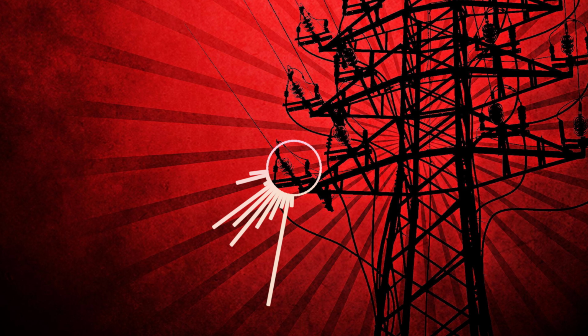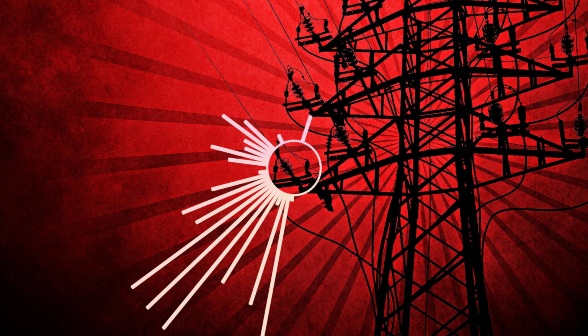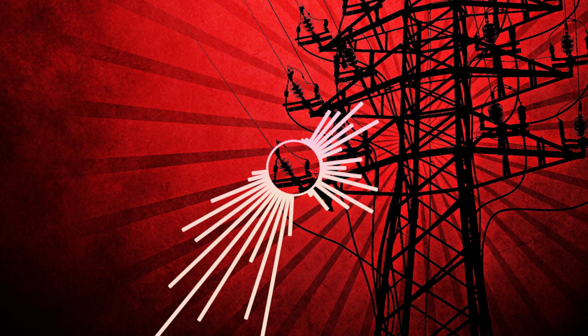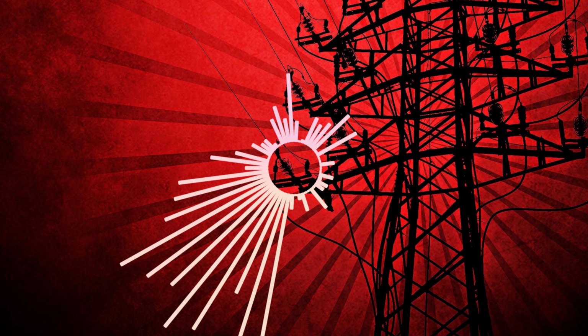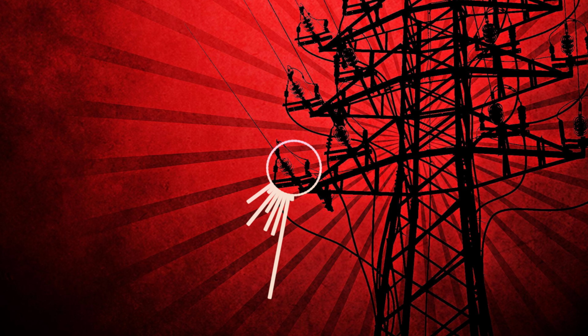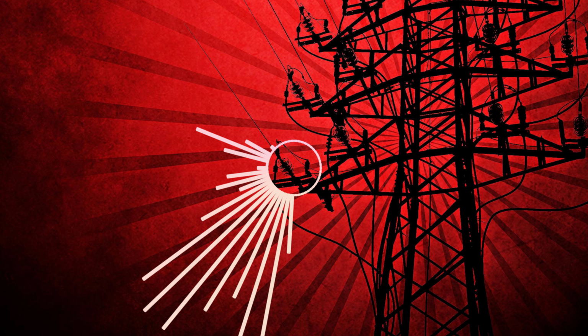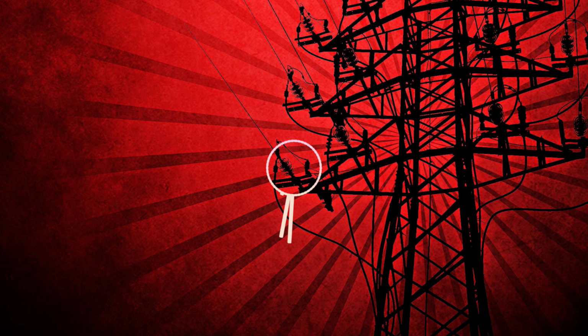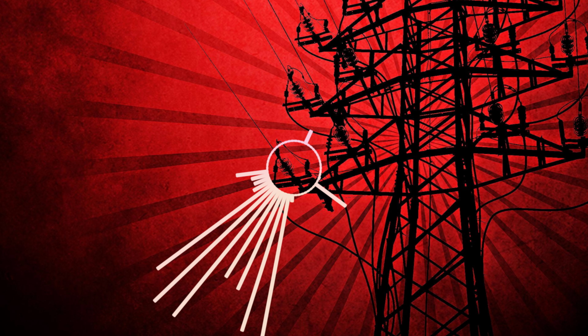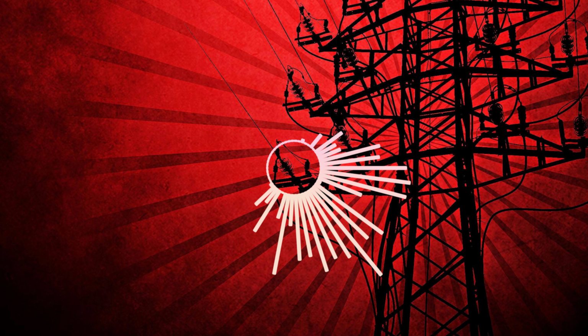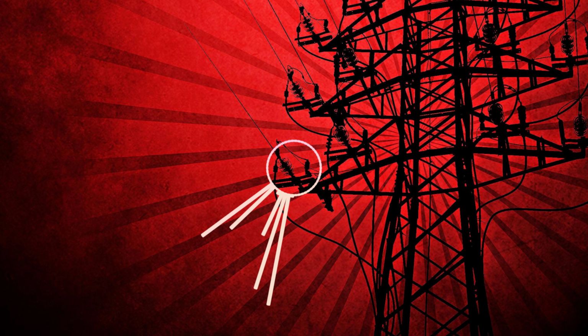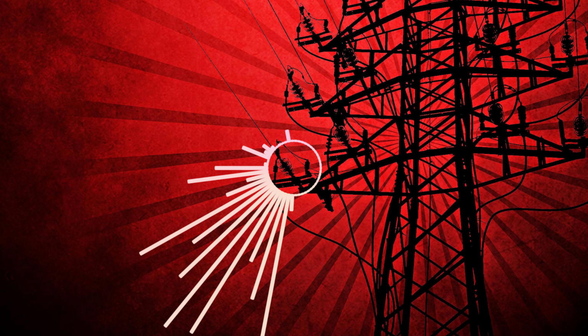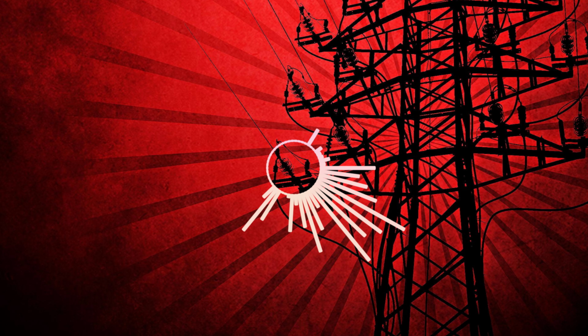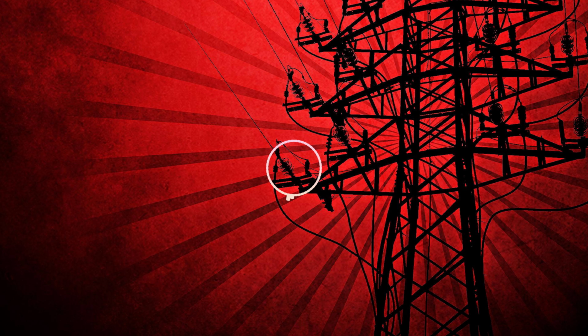Let's work through a real-world example. Say you're working on a power distribution room in a large commercial building. You have been asked to install a 480 breaker panel, but in the same room there's a large cabinet that feeds a 4160 volt motor control center. Now, the room is big enough for both pieces of equipment, but here's the problem. If there's no wall, locked barrier, or full-height partition separating your low voltage panel from the high voltage cabinet, then you're not compliant with NEC 110.26(A)(5). Even if the space looks big enough, you still need to make sure that each type of equipment has its own dedicated working space, separated from each other by physical partitions, secure doors, or even by locating the equipment in separate rooms.